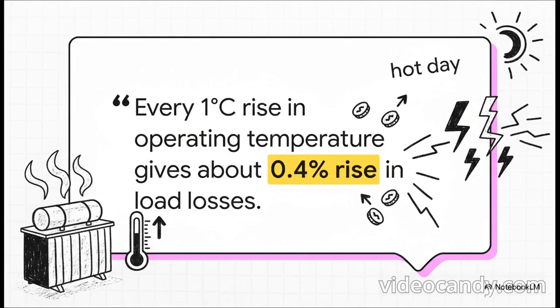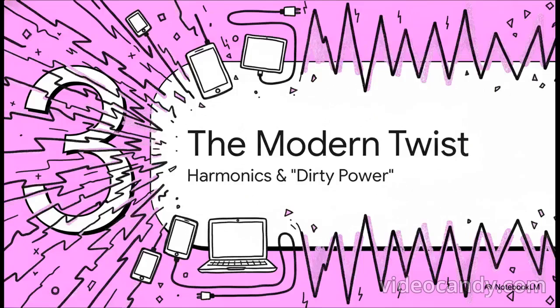The data shows that for every single degree Celsius the operating temperature goes up, the load losses jump by about 0.4%. Now that might not sound like much, but just imagine a heat wave during peak summer demand. Those degrees and those wasted watts add up incredibly fast, driving up costs and straining the grid right when it's most vulnerable. So, as if managing load and heat wasn't enough of a challenge, our modern world has thrown a brand new wrench into the works.